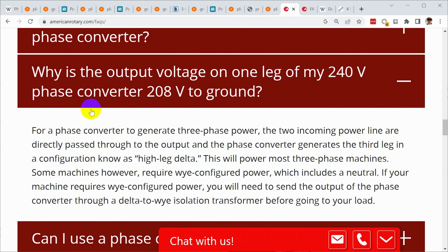They've got a couple of questions out here. One is, why is the output voltage on my 240 volt phase converter 208 volts to ground? And the answer that they give is that they're passing the two incoming power lines directly through and generating a third leg. And they're calling out that this is a high leg delta configuration. This will power most three-phase machines.